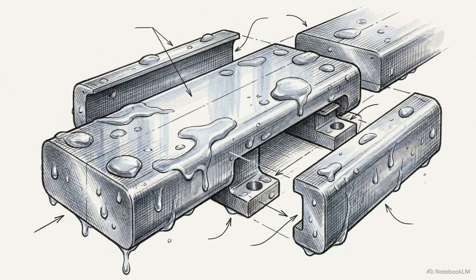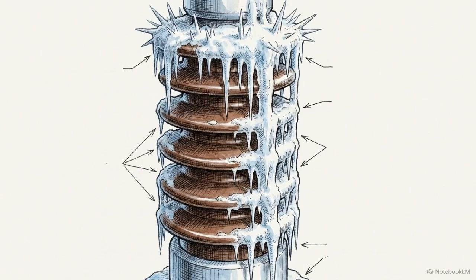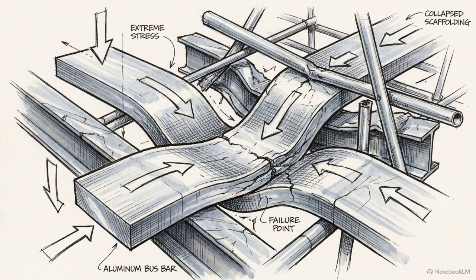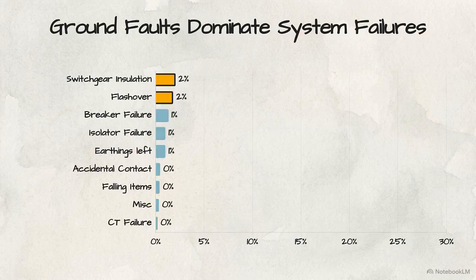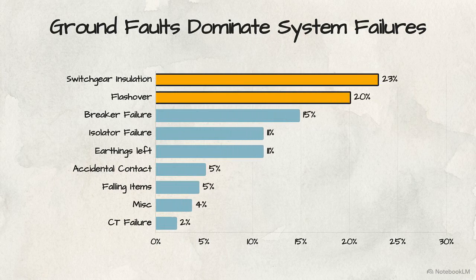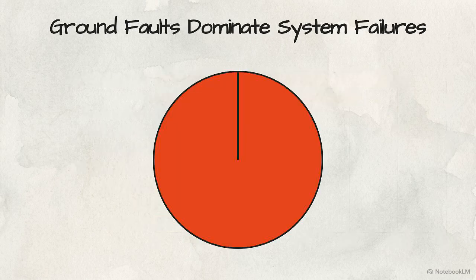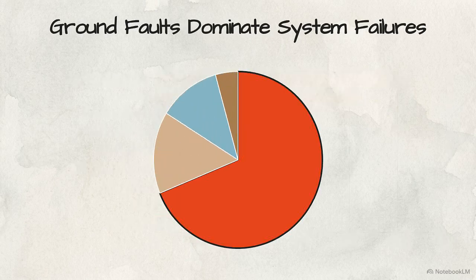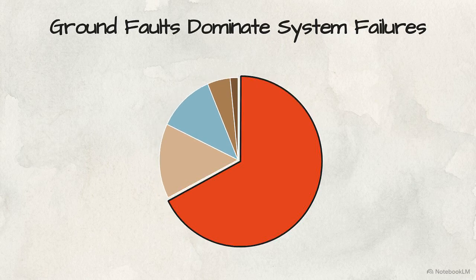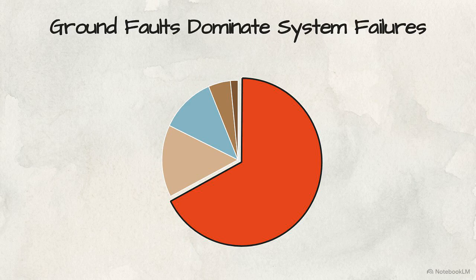They sit outdoors, subjected to extreme environmental stresses, constant lightning strikes, and immense mechanical forces. This bar chart outlines the empirical threat model for busbars. The data shows that 2% of all faults originate from electrical flashovers, while 2% are caused by the failure of switchgear insulation. Zooming in on the specific nature of these events, we see the most dominant failure mode by far. Over 67% of all incidents are single-phase to earth faults, typically caused by a line shorting out to the ground.